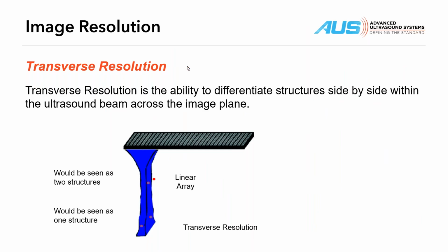In order to measure transverse resolution, you're really talking about a 3D, 4D probe. And it's not something that anybody's ever required to measure by any kind of accreditation, such as the American College of Radiology or the Intersocietal Accreditation. So it is a way for you to evaluate 3D, 4D imaging if you have a system that does that. But there's no accreditation requirement to report or measure on that.